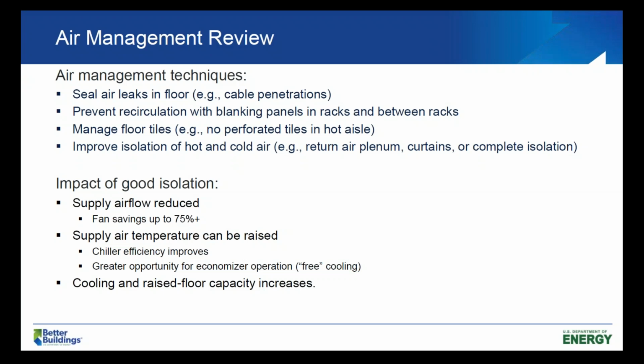And the impact of that can be very significant. You can reduce the supply airflow, saving most of the fan energy. You can increase the temperature of it as well, which improves the efficiency of the system and plant, and you increase the capacity of the system, as well as making your IT equipment happier, because you're better complying with the thermal guidelines. Next slide, please.